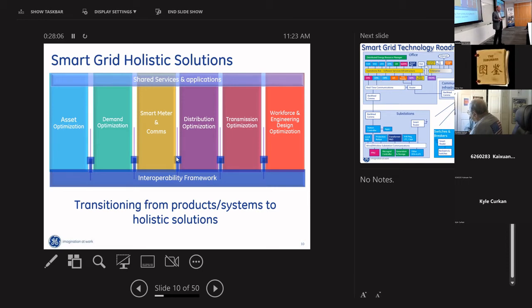Next is demand optimization. We're aggregating load and demand, and today in an EMS, in a generation and transmission control center, we use aggregated load as a dispatch tool rather than traditional automatic generation control, ramping units up and down. It may be more economic to pull the trigger on some load for a lot less money instead of moving a unit into a less efficient operating zone.